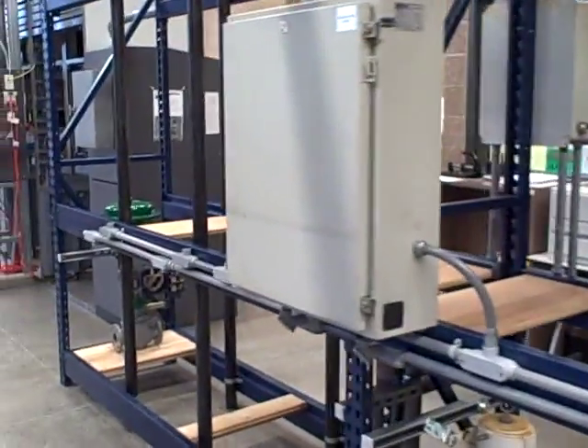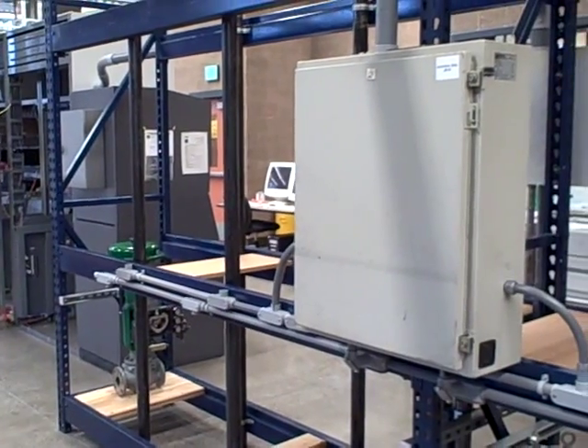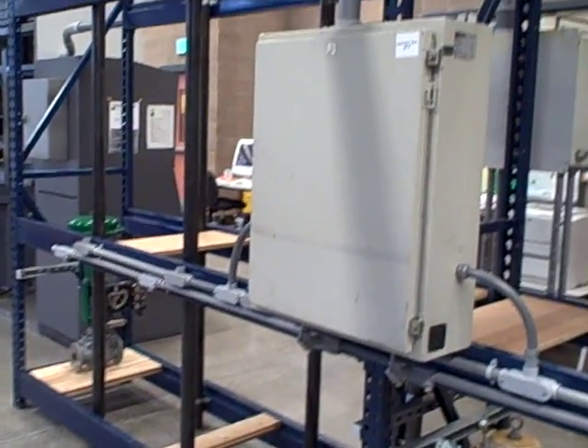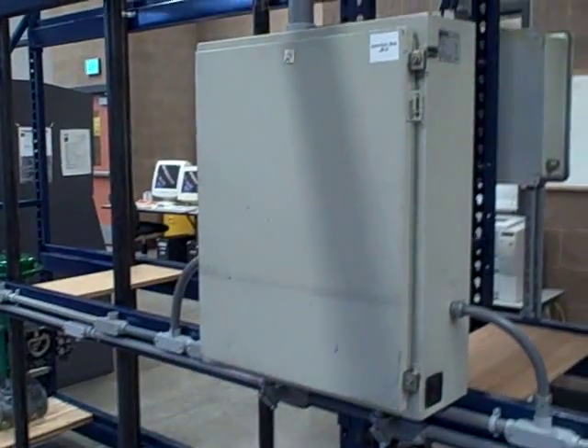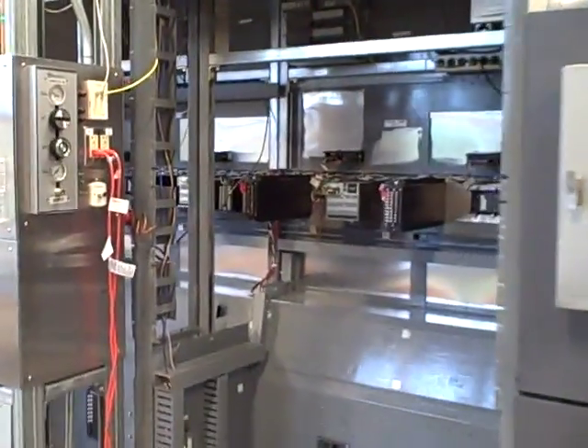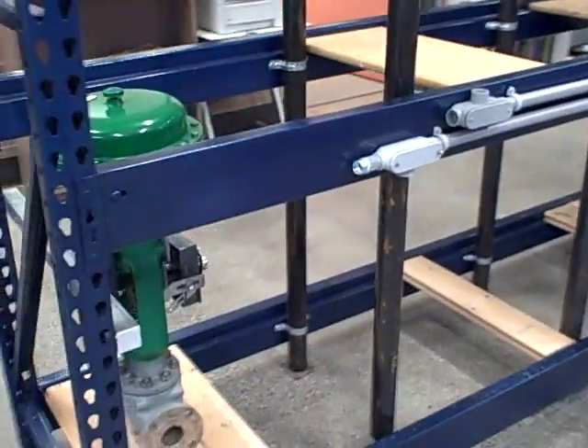For those not familiar with how my students do lab work here: we do not use pre-built simulators or trainers. What we do is build working instrument loop systems, starting with this as an infrastructure. Students have a place to bolt instruments, panels to pull wires to, and to marshal their wiring. They also have control systems like the DCS and the control panel that they can use as control devices for their loops. They actually build the loops — they mount the field instruments, pull wires to the controllers or the DCS, configure the controllers, run wires to the control valves and I/P transducers, and create working loops.